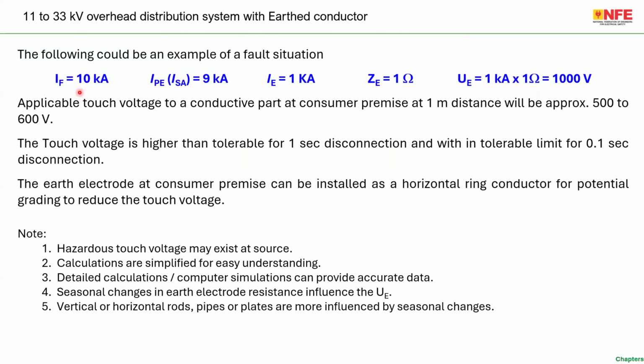Example I am just putting. The following could be an example of a fault situation. I have taken a very high level of fault current, 10 kiloampere, which is most of the time practically very high. IF, just for your information, let's say 10 kiloampere is the fault current. IPE, actually it's ISA. IPE, imagine it is 9 kiloampere. The current through the earth electrode is 1 kiloampere.